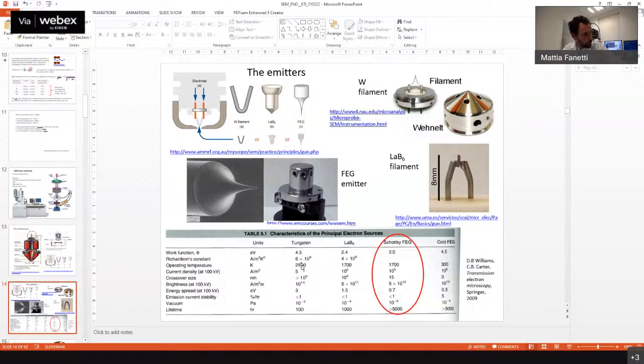It is true that in the old SEMs, in particular the ones that are not required for a very high resolution, the tungsten tip is somehow an economy solution, no? For the microscopes which are meant to work with a bit less resolution and maybe high current. Okay, so this is an economy solution, and the resolution is also much lower in the tungsten case, typically maybe 20 nanometers, even more. And so anyway, the vacuum is required for that.